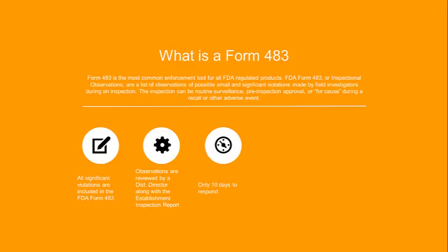And that response only has 10 days to be drafted, and that's a very critical and short time frame to provide a response, but that's the time that the FDA gives you. Significant violations will lead to a warning letter, so does a poor response. If a response is fired off as soon as you get the Form 483, then the FDA is left with the impression, and this is from conversations we've had with many compliance directors in the district offices, that the facility doesn't understand the magnitude or the ability to correct these issues in a longer time frame than that one-day response.